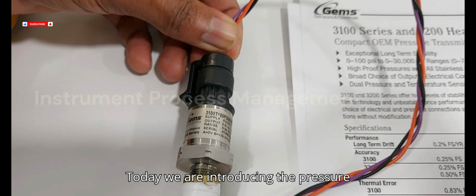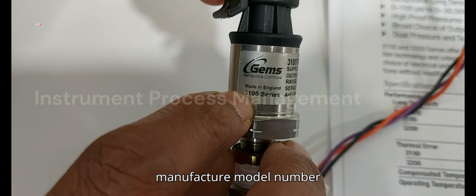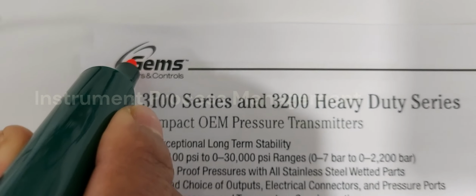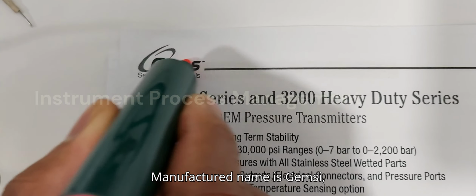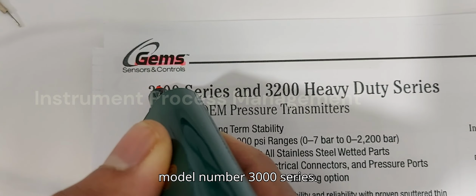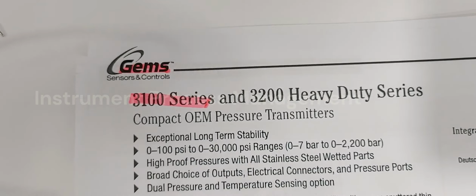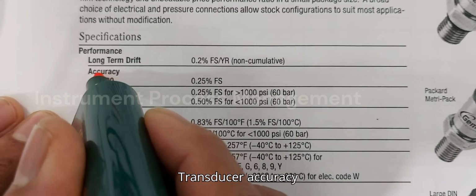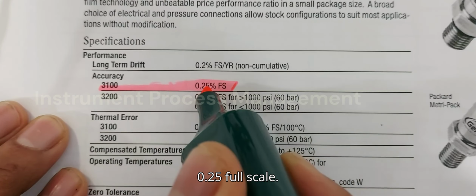Today we are introducing the pressure transducer calibration. Manufacturer, model number. Manufacturer name is Gems. Model number 3000 series. Transducer accuracy 0.25% full scale.